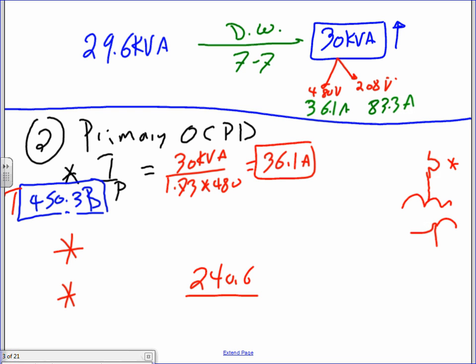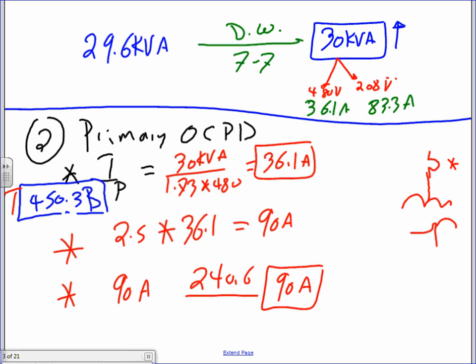When you guys go to the table, this transformer has primary only protection. On the secondary, there's nothing. There's one downstream. So we're going to multiply by 2.5. My multiplier would be 2.5 from table 450.3(B). Multiply 2.5 by 36.1. If you do your math, you're going to end up with 90 amps. Then you take the 90 amps to this section, and it gives you a 90 amp circuit breaker. And if it's not a standard size, you're going to go down. The maximum circuit breaker that you can put is 90 amps. Any comments, guys? Any questions? Where did I get the 2.5, Karen, from the table that you're looking at?